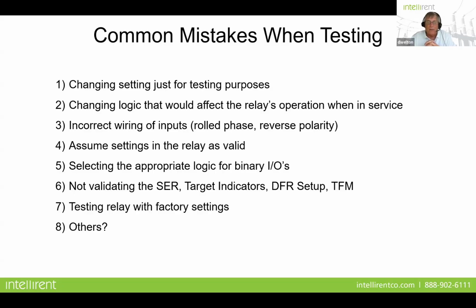He said, we tested it on the bench. We tested it with everything was fine. And I said, how did you test it? Well, we tested it with the software that we use that takes the settings out of the relay, configures the test, and then applies the right values. I said, okay, well, we better go into the relay and look at the settings. And sure enough, they had rolled the CT values. Okay, so my point is this: if you don't validate the settings in the relay and somebody makes a mistake in putting in the wrong values, the relay is going to fail.